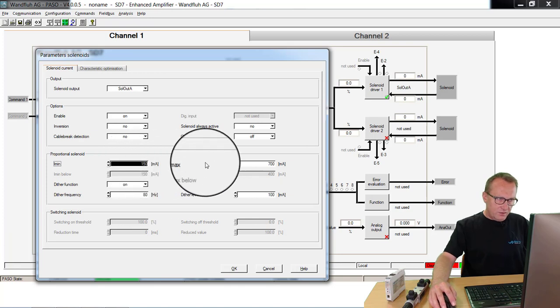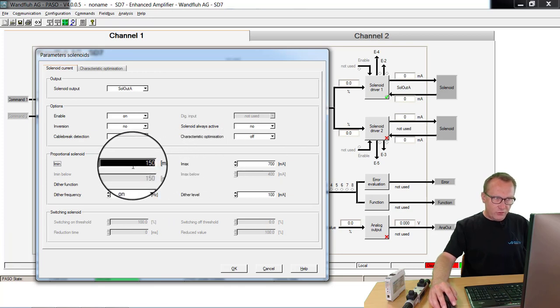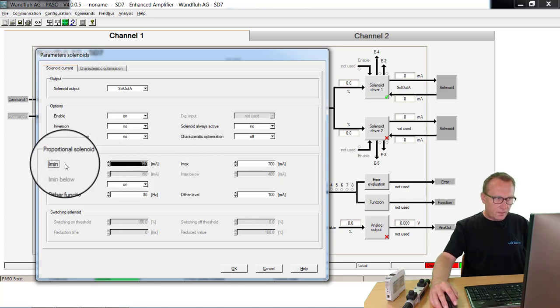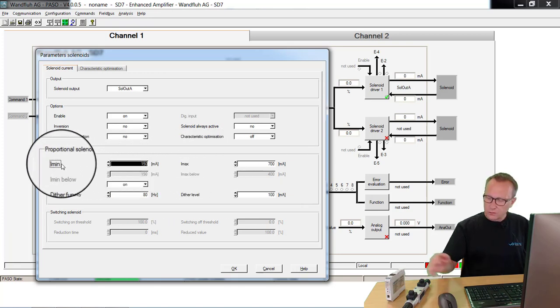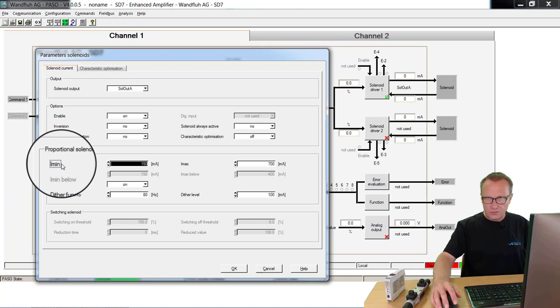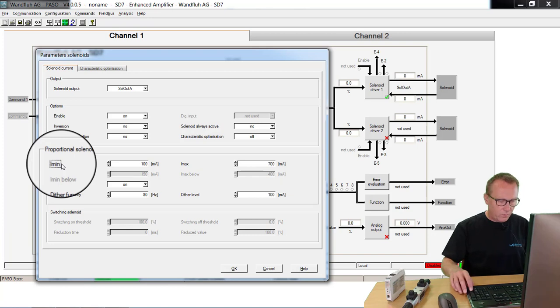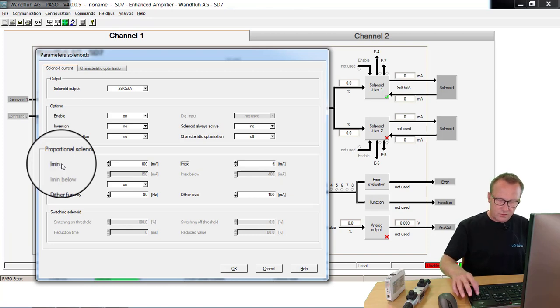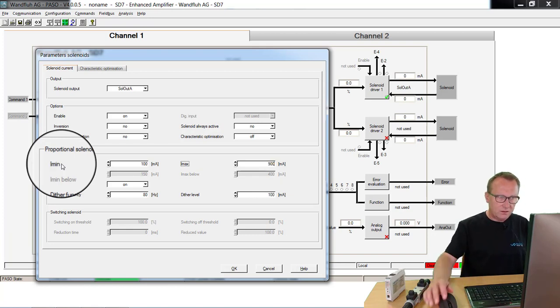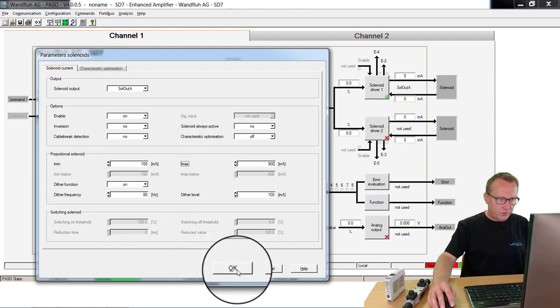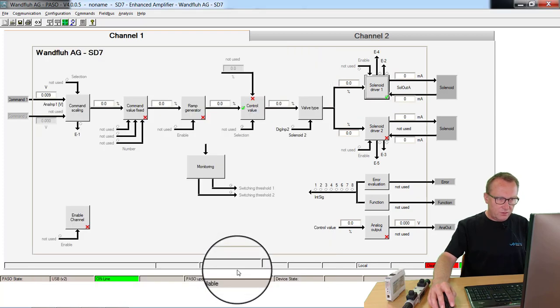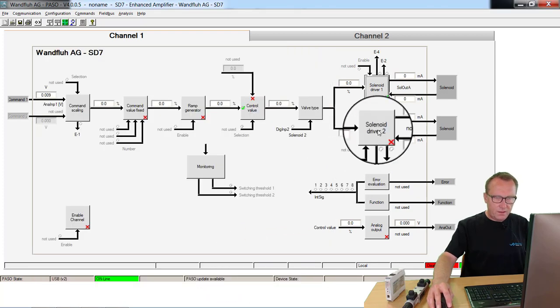These values you can read out from the datasheet from the used valve type. For our example we take for I-minimum 100mA and for the I-maximum 900mA. If it's correct click to OK.